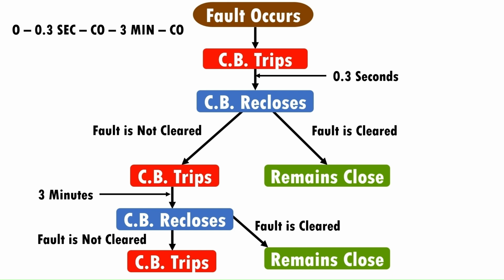So friends, the auto recloser improves power supply continuity by quickly restoring power after transient faults. It eliminates the need for manual intervention for most common temporary faults, which saves time and operational cost. That is the role of the auto recloser in modern power systems.